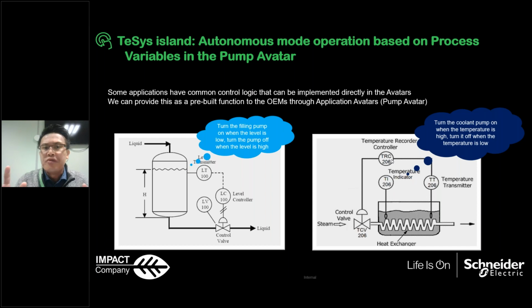So what we call configure, we are not programming, because we are not using the ladder program for the PLC. No need to program in the TeSys island. You just need to configure with the selection table. So it's very easy, and all the configuration software is free. It's free of charge. Actually, it's free to download on our website, and then you can just go to the software and configure it with a different selection table.